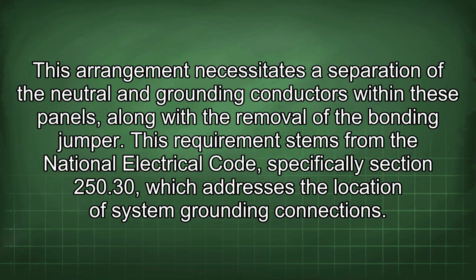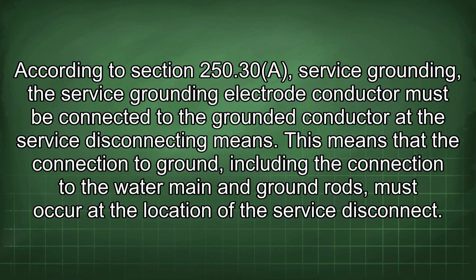This requirement stems from the National Electrical Code, specifically Section 250.30, which addresses the location of system grounding connections. According to Section 250.30(a), the service grounding electrode conductor must be connected to the grounded conductor at the service disconnecting means. This means that the connection to ground, including the connection to the water main and ground rods, must occur at the location of the service disconnect.